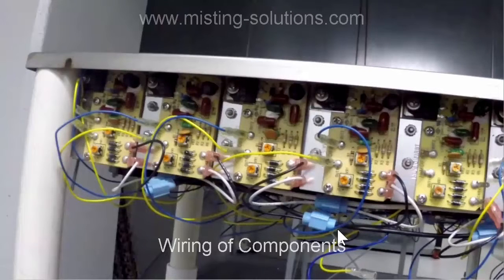Now we're going to talk about wiring it back up, because there is a particular pattern to the wiring. And you can see here, we'll take this middle one here, that you've got a blue wire here and a yellow wire here, and this blue and this yellow wire are connected to the transducer nebulizer itself. So, as you probably saw earlier, each one of the transducers has a blue and a yellow wire on it. Now, they always go in this particular order. Let's say that the yellow one is always the closest to the edge, and the blue one is always in the middle and closest to this, I forget the name of it, but this is a driver chip here. So the blue one's always in the middle, and the yellow one's towards the edge.